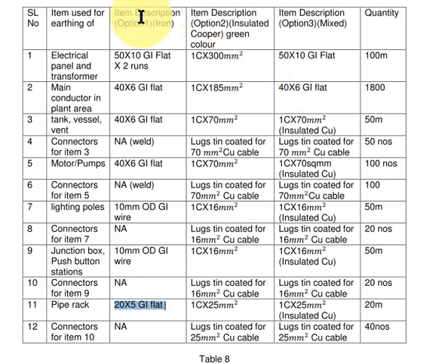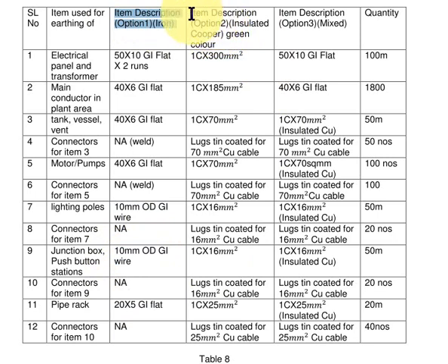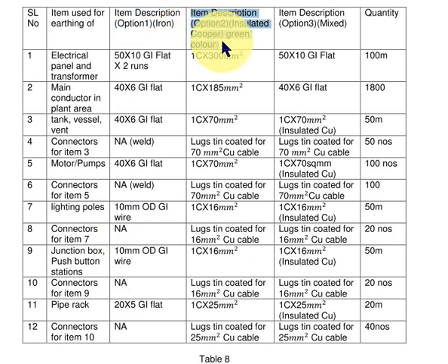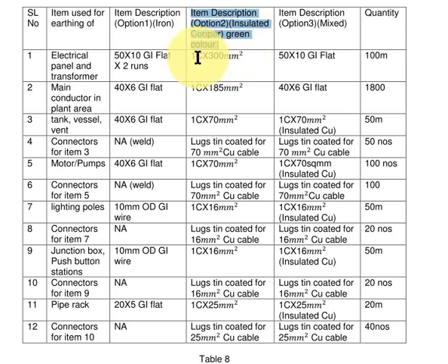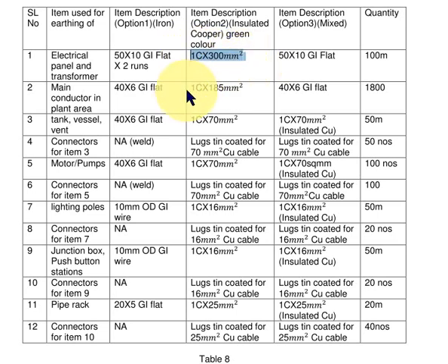Now this is the option where we use only iron conductors, and there is one more option of using only copper insulated conductors. We do not prefer copper in the main plant area because of cathodic protection, but some owners do use this. So inside the electrical room, 300 mm² copper was used. Inside the main plant area, 185 mm² copper was used.